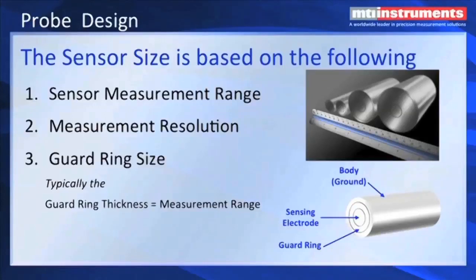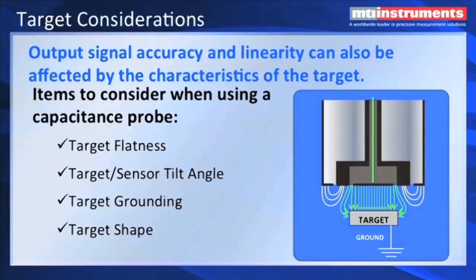And then we have a third element that's called the body, and that's grounded, and that's how you grip the probe without shorting out the guard ring. Some things we also need to address is the target shape. Different shapes will create fringing effects, and typically we like to have a target that's bigger than the probe. The smallest you want to make a target is about the diameter of the probe.